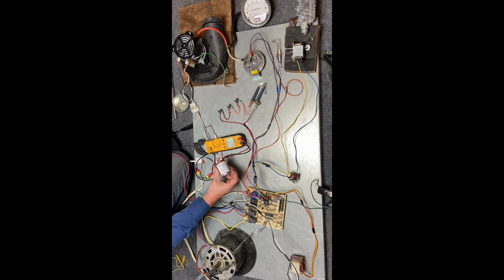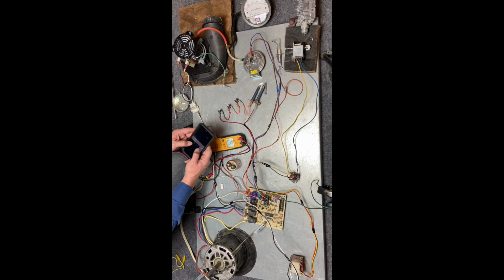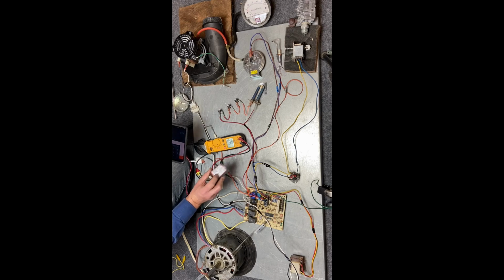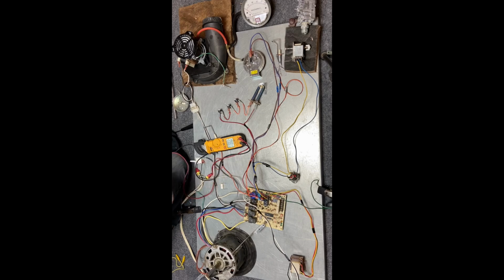So we're going to read on the capacitor itself, and the capacitor is rated for 7.5 microfarads with a plus or minus of 10%. So let's see if that capacitor is within range. What we're going to do is use a calculator. And we know at 10%, so I do 7.5 times 10% equals 0.75. So that means I could be as high as 7.5 plus 0.75, 8.25, or as low as 6.75 and still be good. So this capacitor, even though it's slightly lower, it is still good because it's within the plus or minus range of this capacitor. So that's how we check the capacitor.